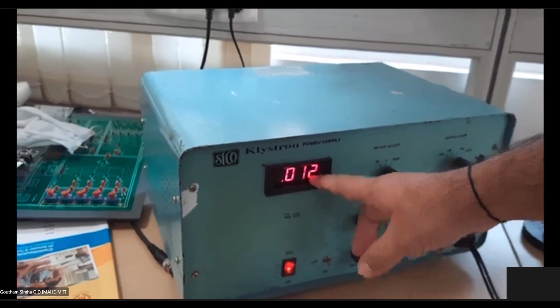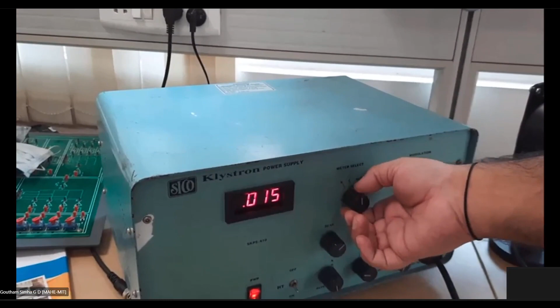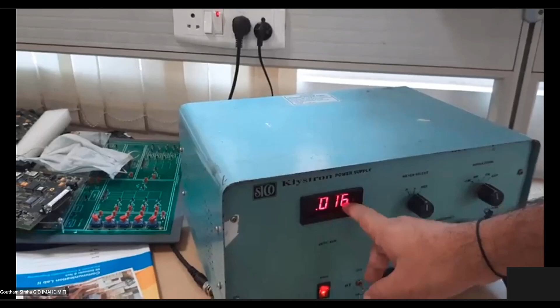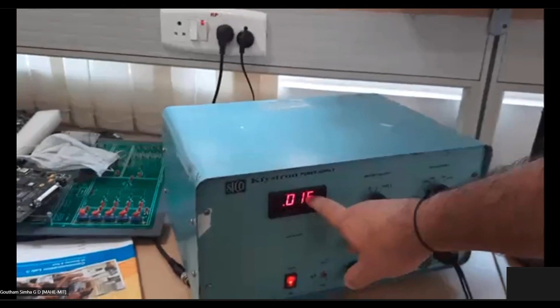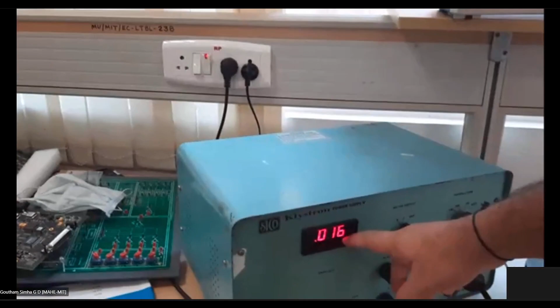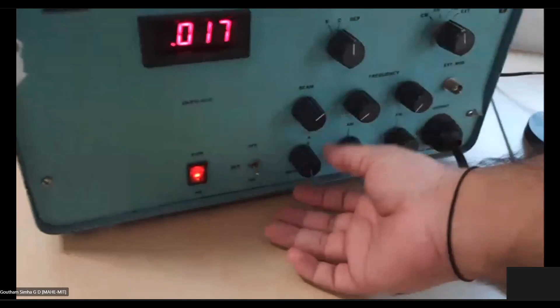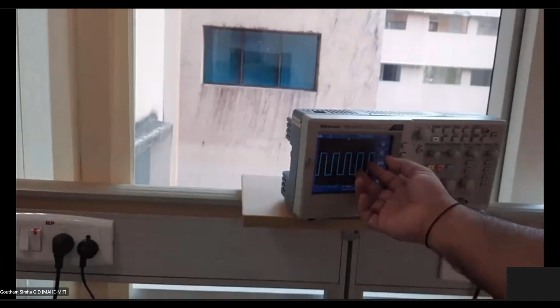You can set this near to the current bar, and it should be between 0.014 to 0.019, that is in ampere. For any value in this range, you will get a perfect square wave over the CRO. If you are not getting a perfect square wave over the CRO, then you have to tune your beam and repeller to adjust this value such that you get a square wave. If you are not getting a square wave, then you cannot move ahead with this experiment.